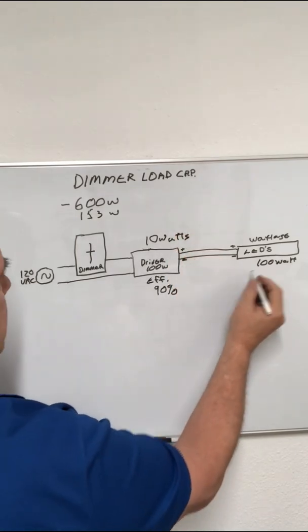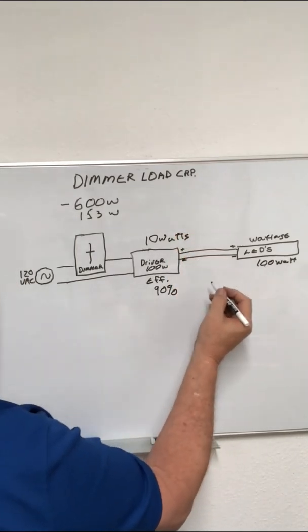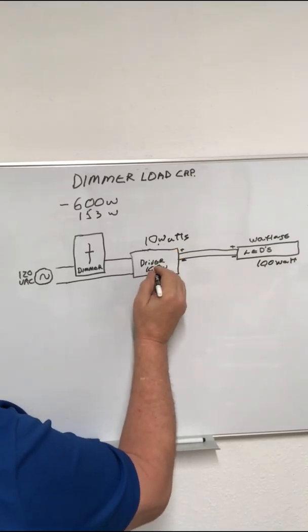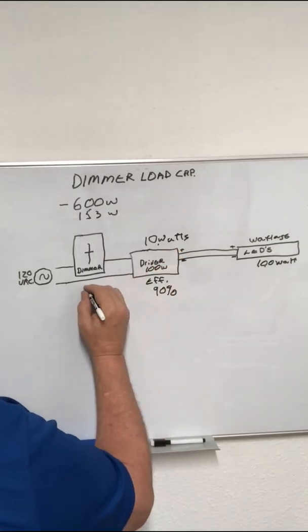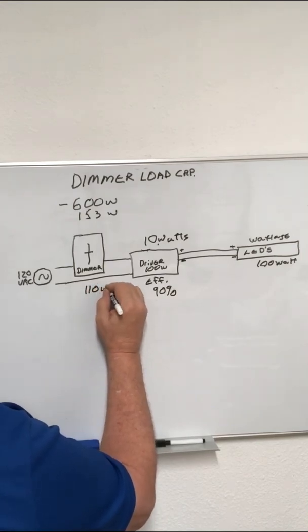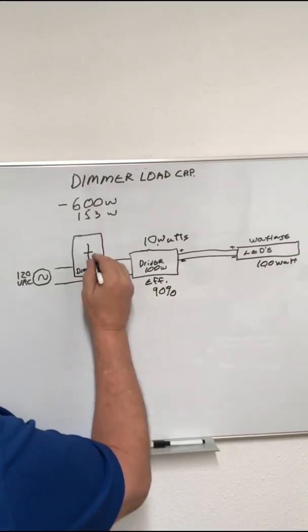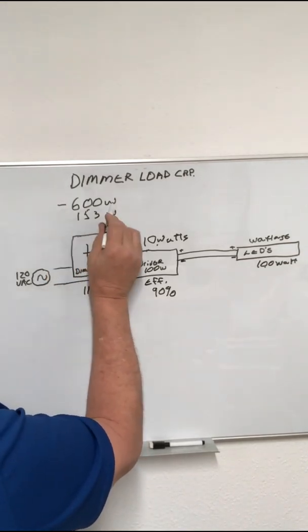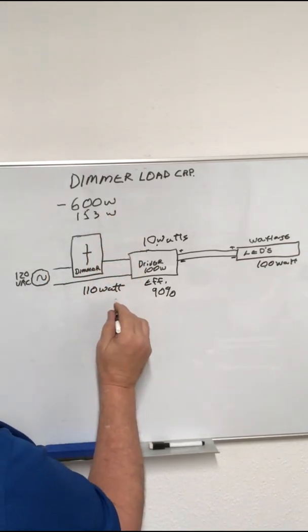So, what you do is you would add the 100 watts from the LEDs and the 10 watts for the driver being consumed by the driver, which gives you 110 watts felt by the dimmer. Now, you see that we have a large capacity here, so we're not even close.